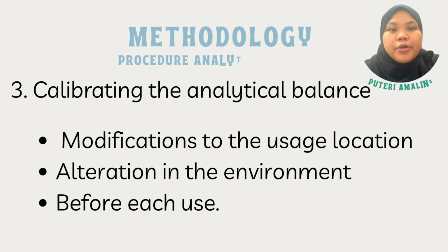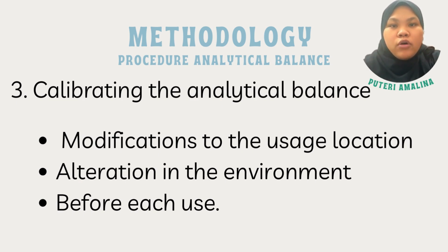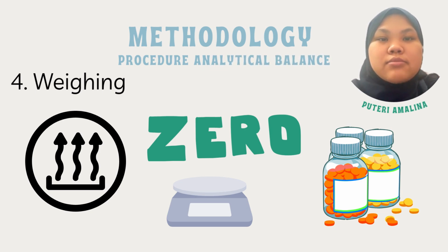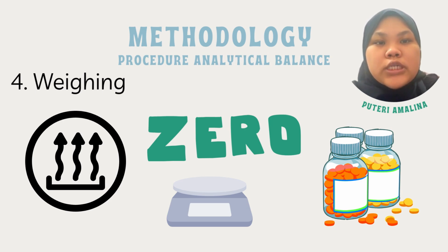Number 3, calibrating the analytical balance. The analytical balance must be calibrated for a sample to be precisely weighed, and these are the circumstances that call for calibration: modifications to the usage location, alteration in the environment, and before each use. Next is weighing. The analytical balance must be preheated for an hour before using it. Set to 0 in the no load condition by pressing the tare button and place the weighing boat at the center of the weighing pan. Avoid putting things in the balance as it can contaminate the balance.